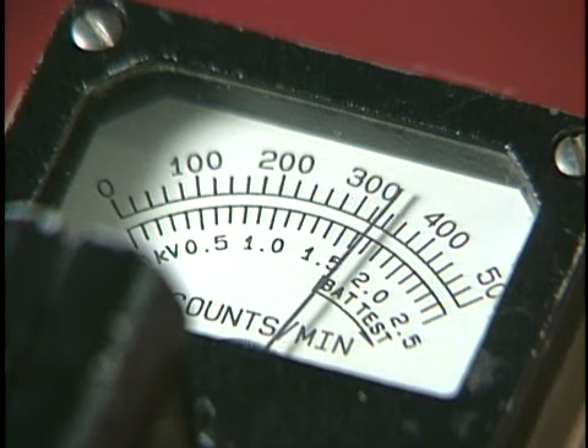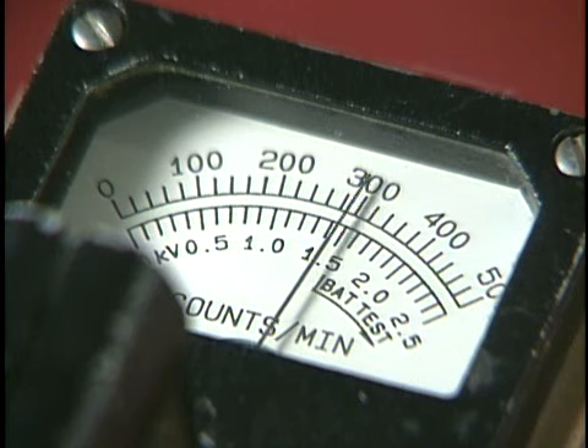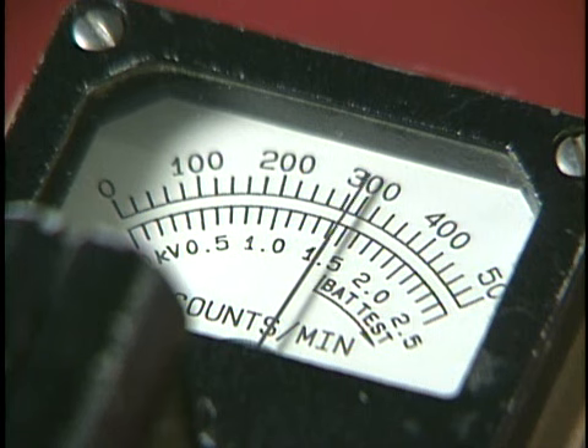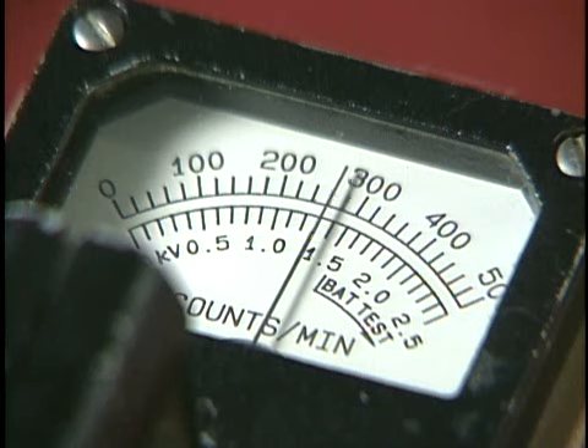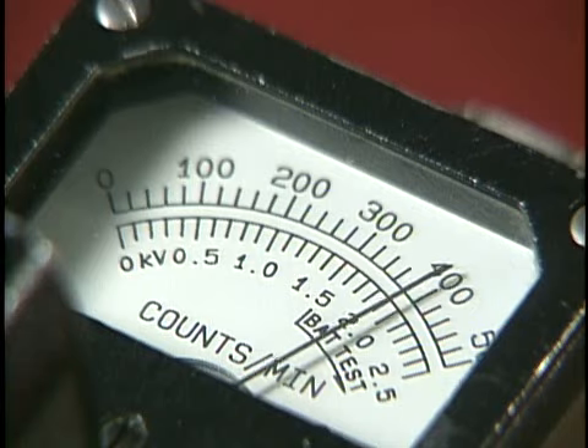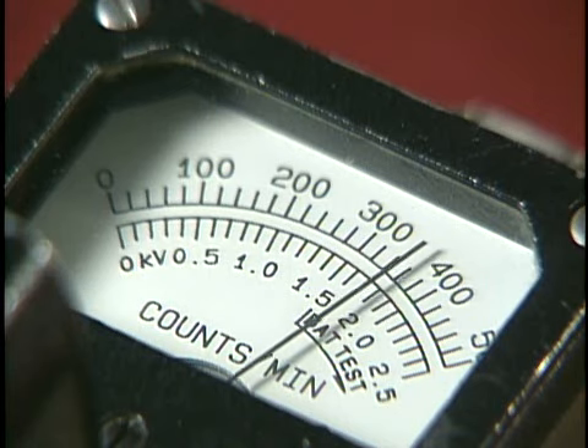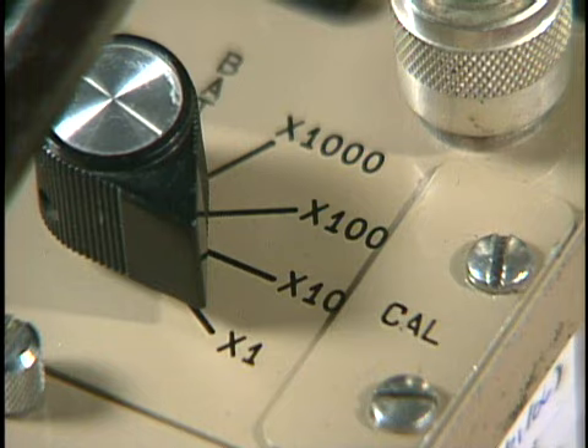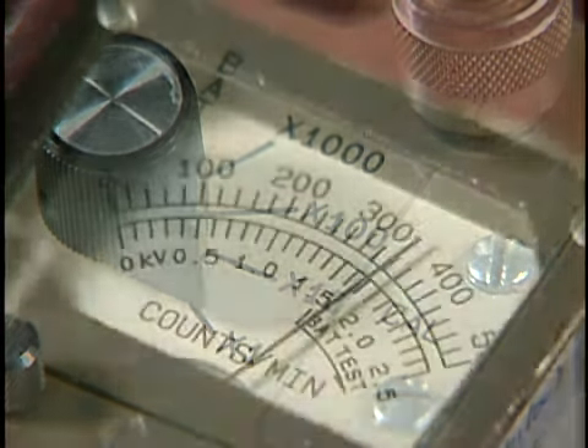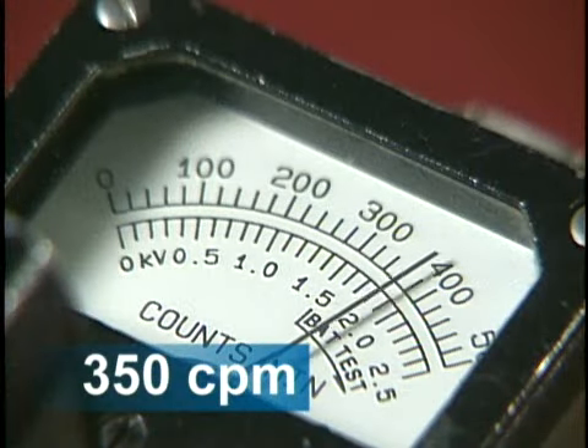Different instruments may display different units, or the same instruments may display multiple units. When using a GM detector, always use the count per minute CPM scale. If your instrument does not have a CPM scale, then use whatever scale is displayed, but always remember to note the units when you record the results. When taking a radiation reading with this type of instrument, remember that you must multiply the reading on the display by the scale setting. For example, this instrument is reading 350 counts per minute. The instrument is set at ×1, so 350 times 1 is 350 counts per minute.